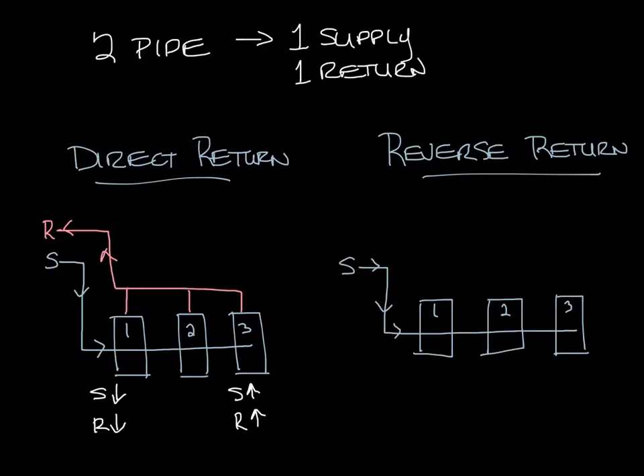So the first unit's return goes the longest, then the second, then the third. So now you can see that the first unit has the shortest supply path but the longest return path. And the last unit has the longest supply path but the shortest return path.